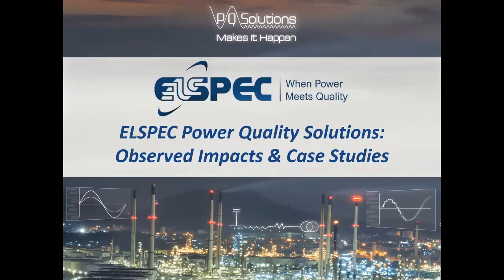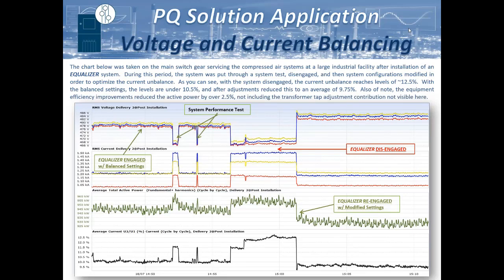So the true benefit of that is really the voltage stabilization that's induced. We're basically mitigating for all of the downstream load demands and creating a lot more strength and stability on that network when it comes to voltage. And there's a lot of secondary impacts as well. We also help not only raise the voltage level to equal the secondary output of the supply transformer and maintain it in a very, very tight range, but we also help better balance those loads, which can have an impact on your equipment efficiency rate, and heat being induced, things of that nature as well.